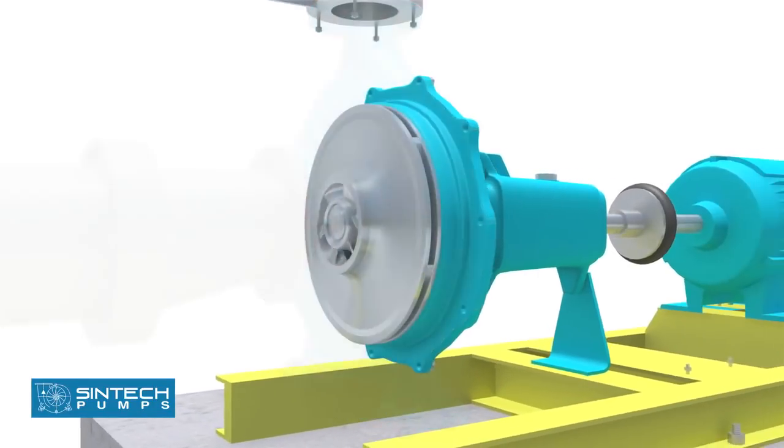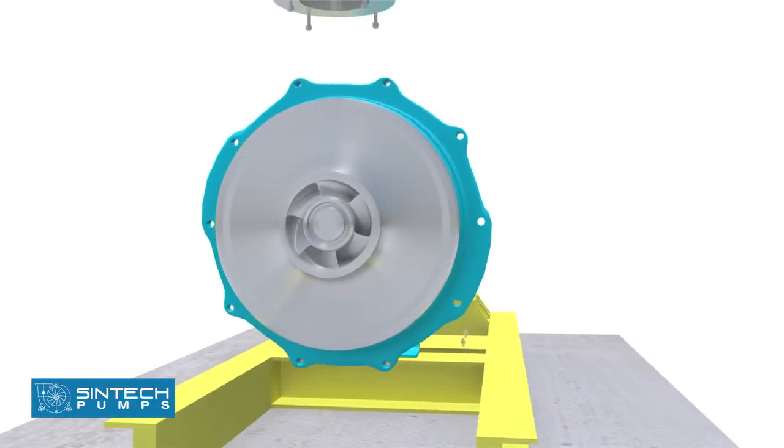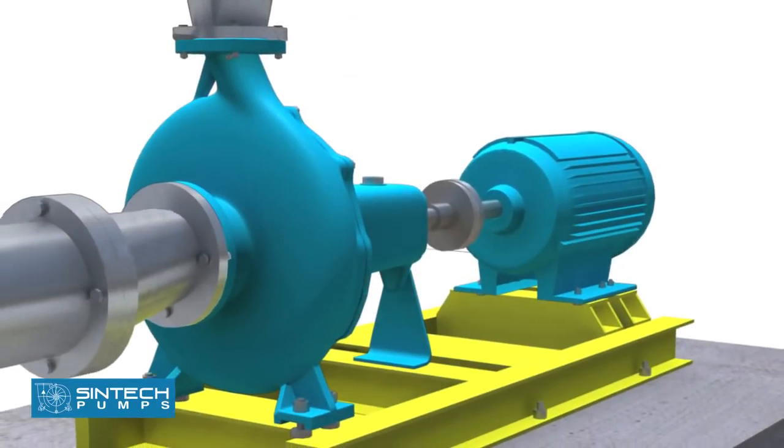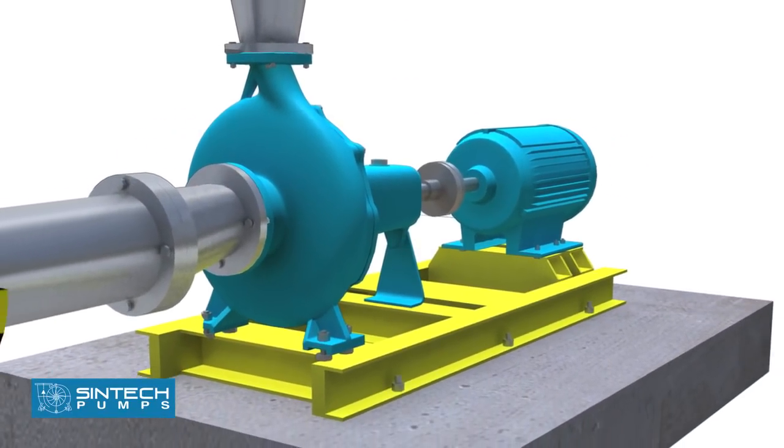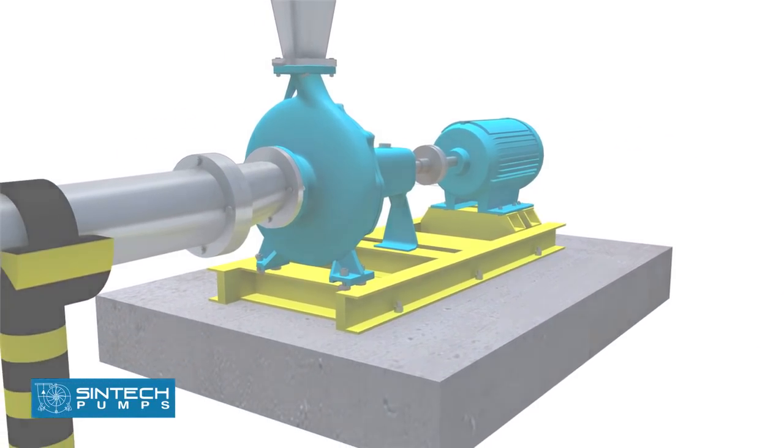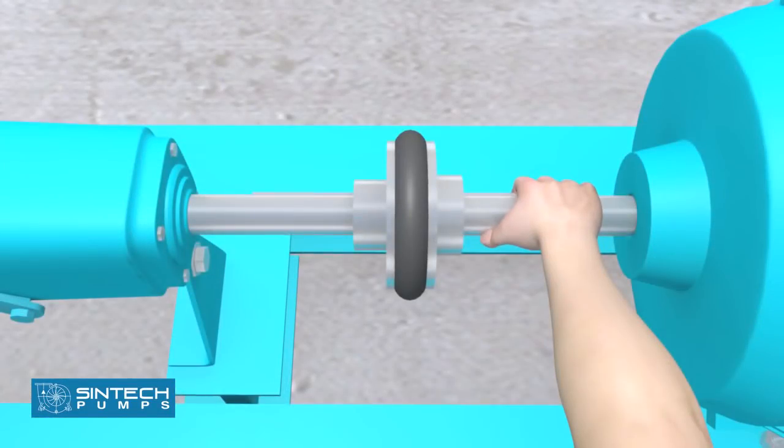The motor should be wired correctly to ensure the correct direction of rotation. This check has to be carried out before the pump is coupled. Once the pump and motor have been coupled, test the movement manually by rotating it by hand to see if it is rotating smoothly.